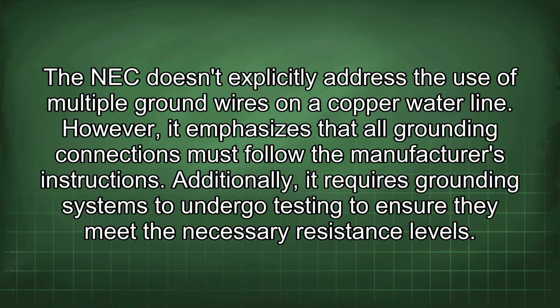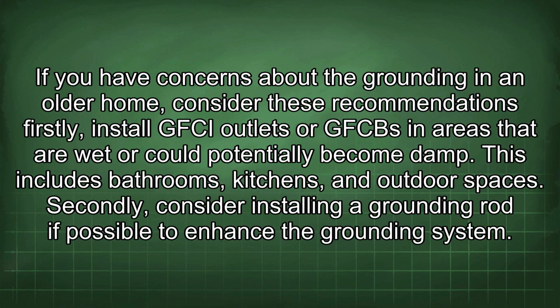The NEC doesn't explicitly address the use of multiple ground wires on a copper water line. However, it emphasizes that all grounding connections must follow the manufacturer's instructions. Additionally, it requires grounding systems to undergo testing to ensure they meet the necessary resistance levels. If you have concerns about the grounding in an older home, consider these recommendations.